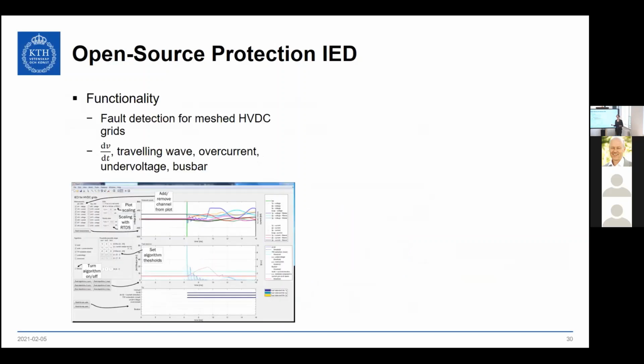What it can do is fault detection for meshed HVDC grids, and the implemented algorithms include DVDT, traveling wave, overcurrent, undervoltage, and busbar protection.